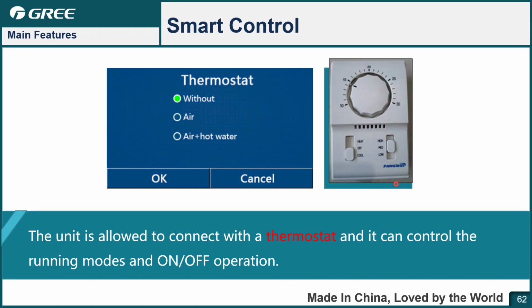Next one is the smart control by the thermostat. If the customer wants control from a thermostat, they can choose this thermostat and connect it with the PCB of the unit, and then set the thermostat. This is the default, without air and hot water. This is for the FCU, air temperature control. This is for air temperature and hot water temperature control. You can set it by your project, and then you can use this thermostat to operate the unit.